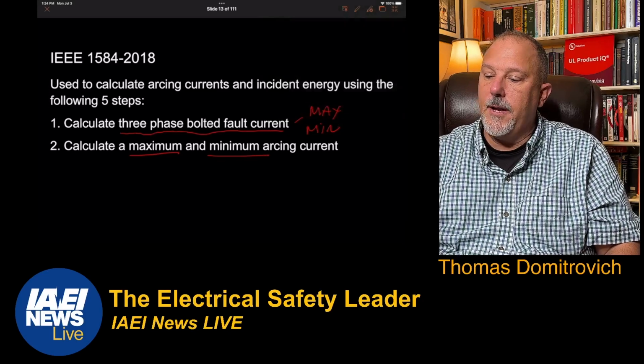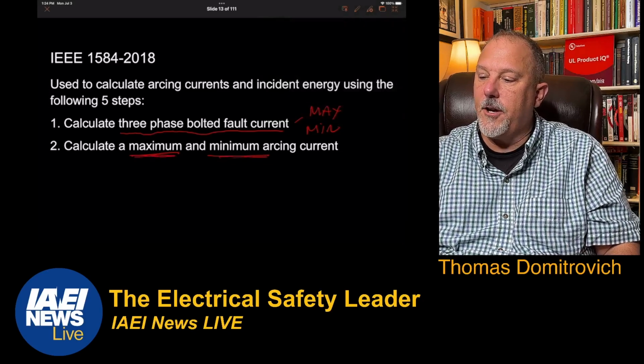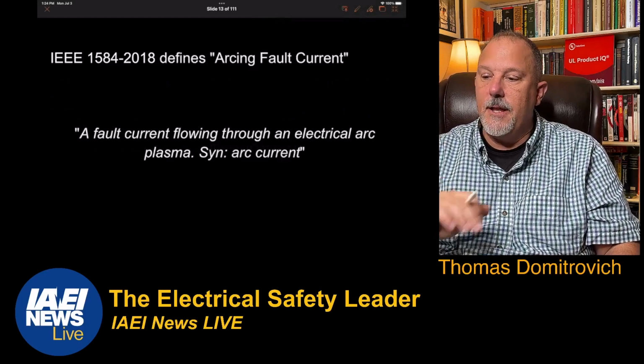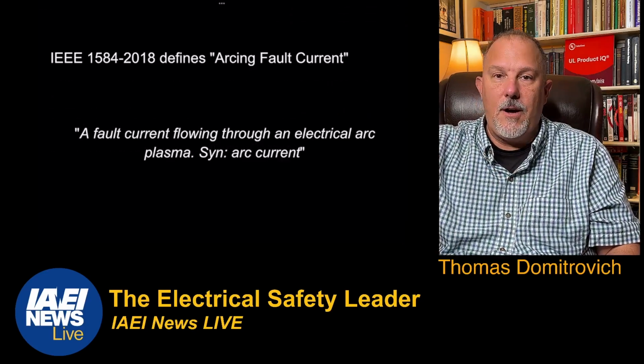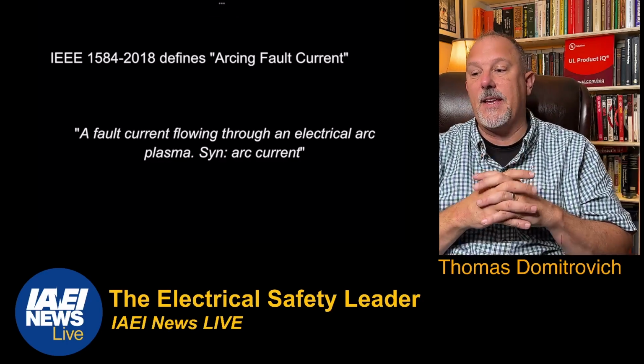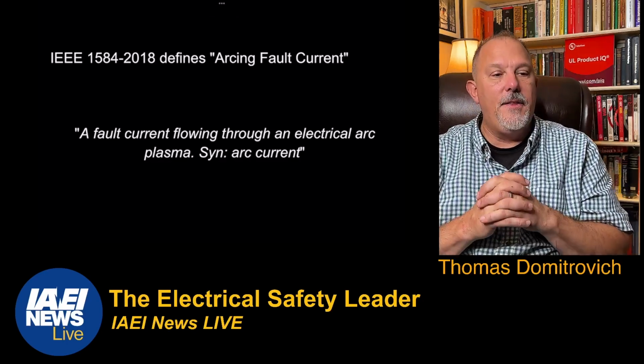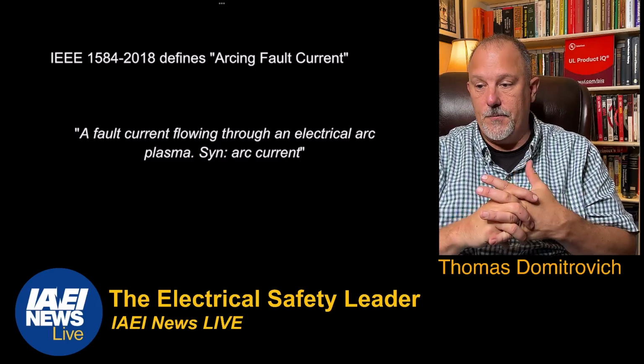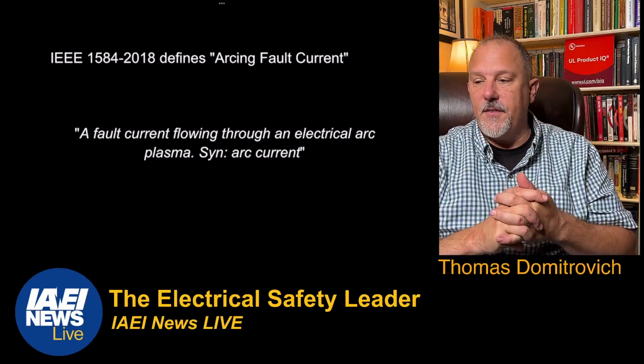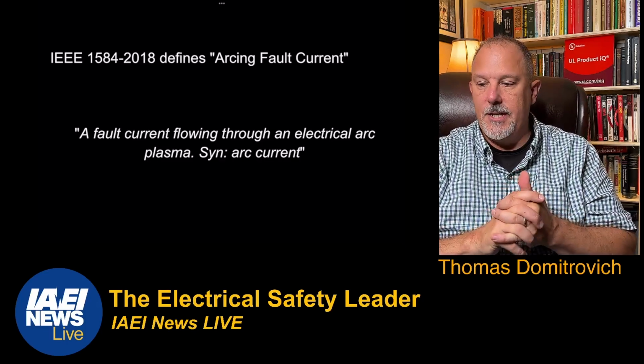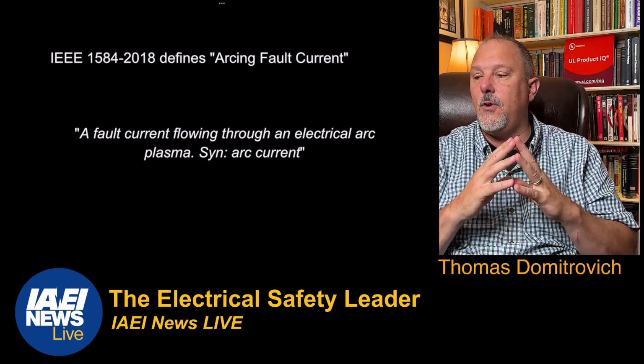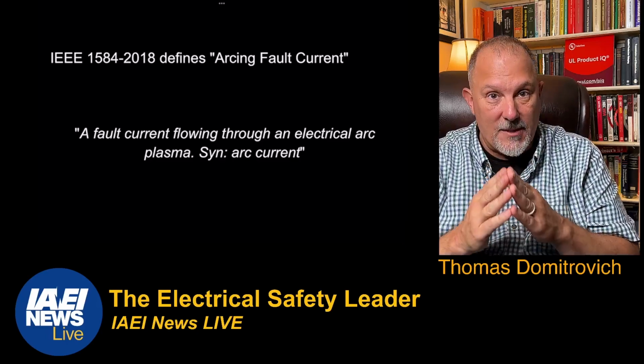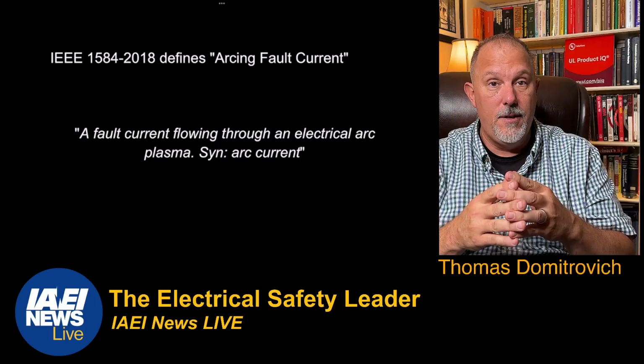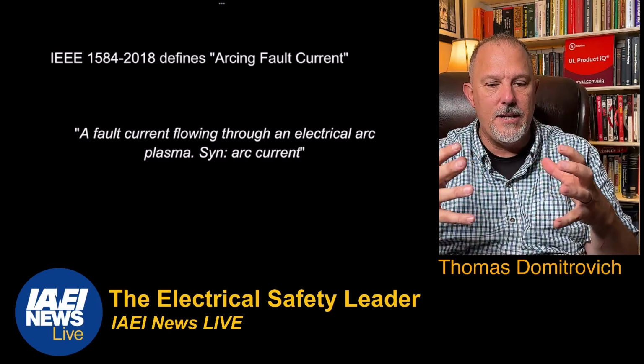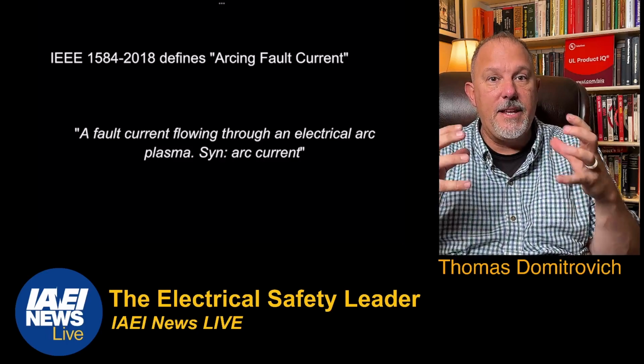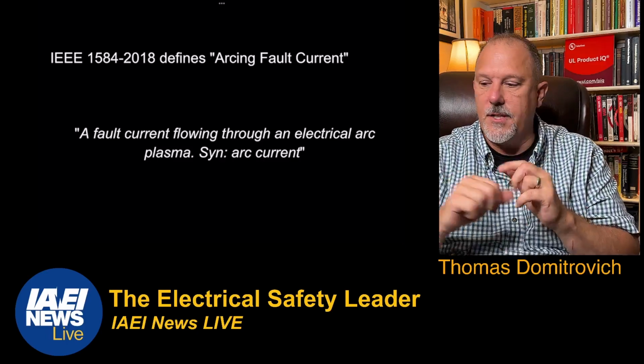All right. So I need a maximum and a minimum arcing current value for each of these. Now, for the second thing, we have to calculate arcing fault current, and this is what I use IEEE 1584 to do. IEEE 1584 tells us that an arcing fault current is a fault current flowing through an electrical arc plasma. Remember we talked about that plasma cloud. That's through air. It's through this charged, ionized cloud of energy that gives the current a path, but there is a resistance.